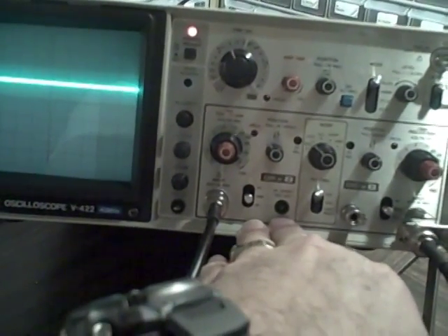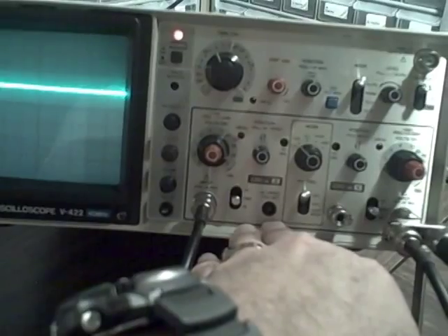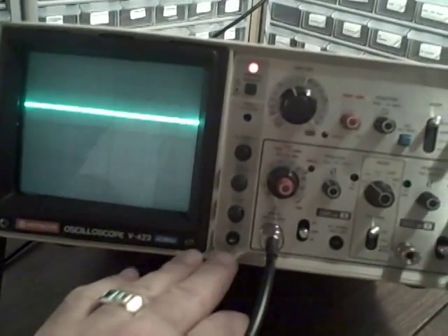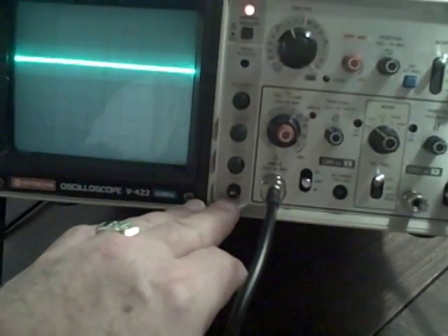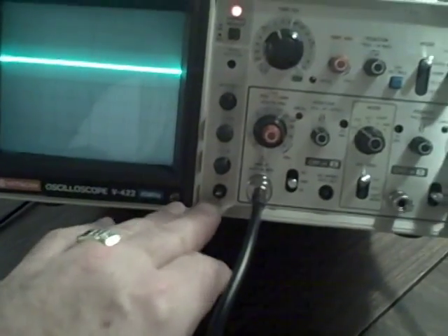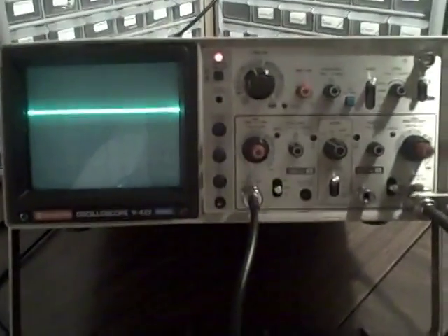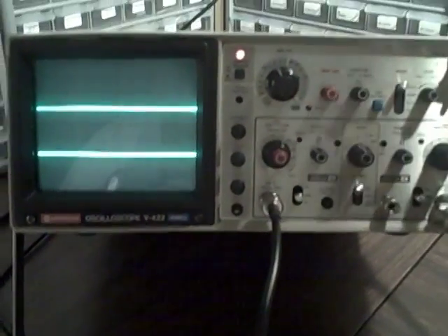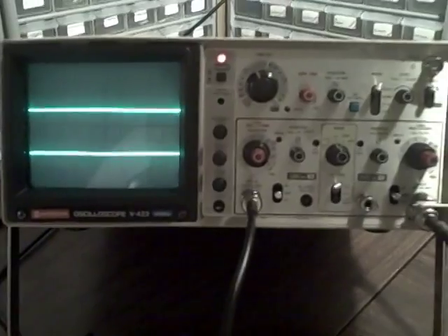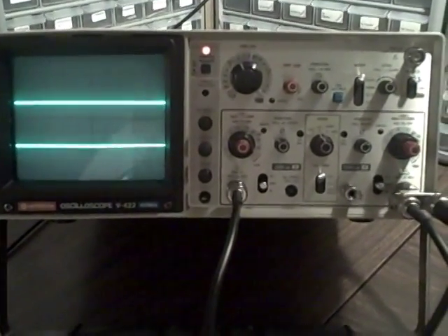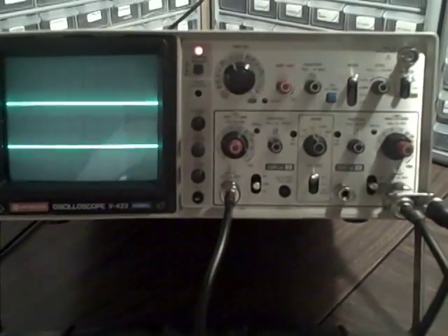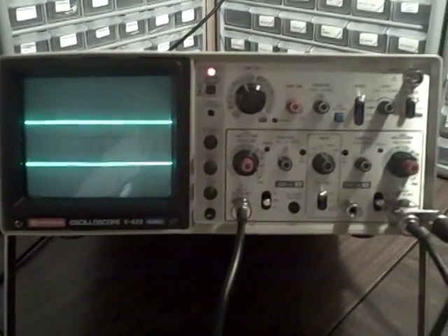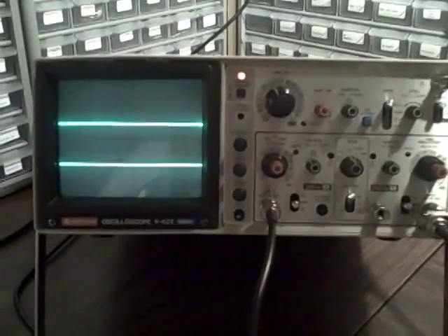We have another calibration called the DC offset voltage output. It's explained in the book. It's part of the calibration procedure. It's available from the front. And then we have a half volt 1 kilohertz calibration point to adjust your probes or take a look at the input signal, whatever. I'm going to go ahead and remove my common connection, and we're going to take a look at the channels independently and prove to you that not only are they calibrated and reading voltages well on all the ranges, but we also have our high frequency response intact. So bear with.